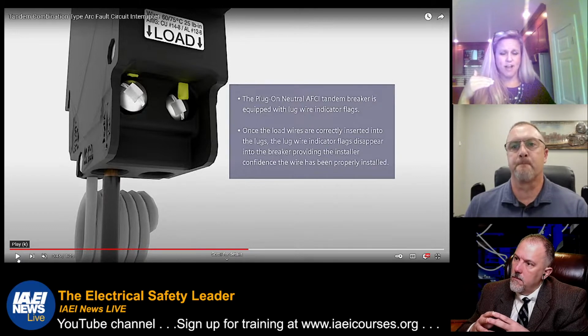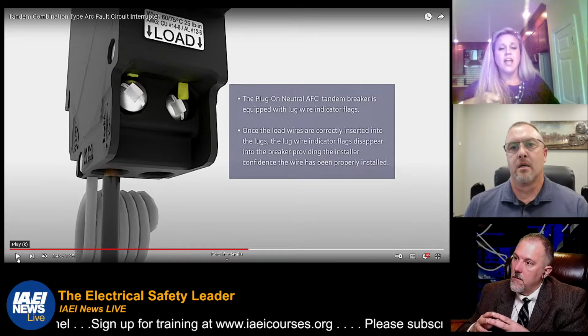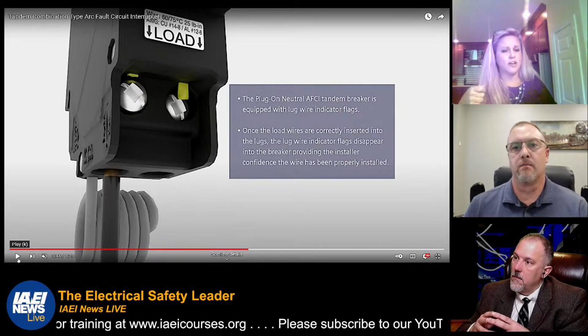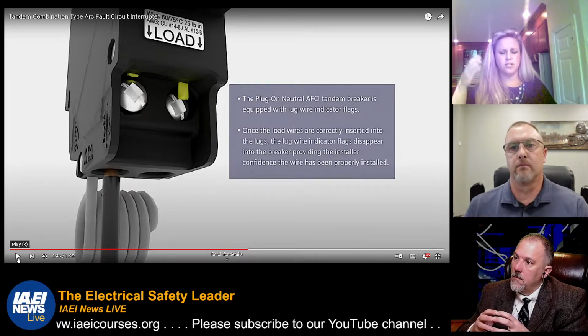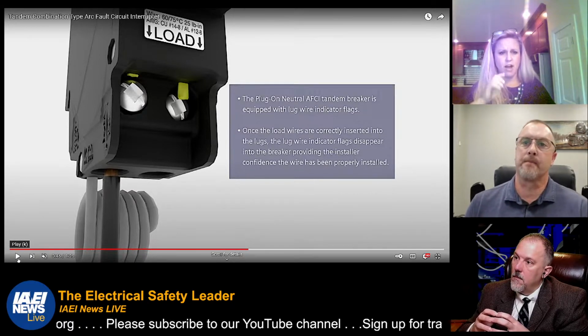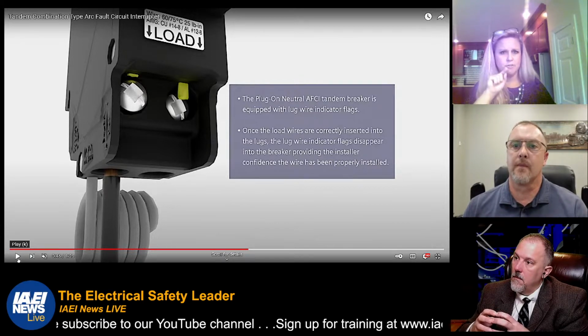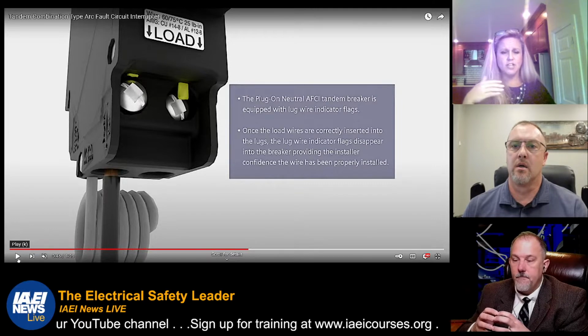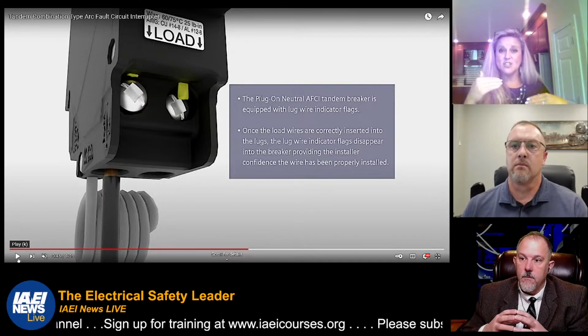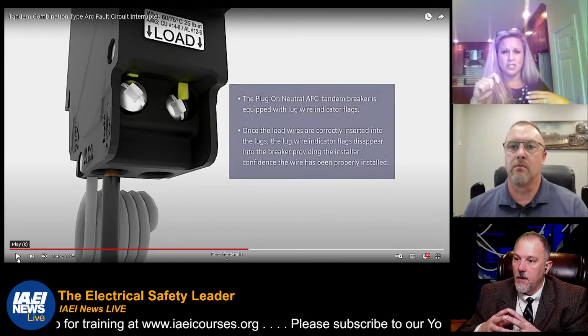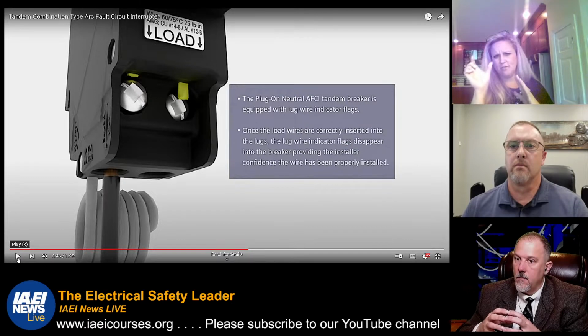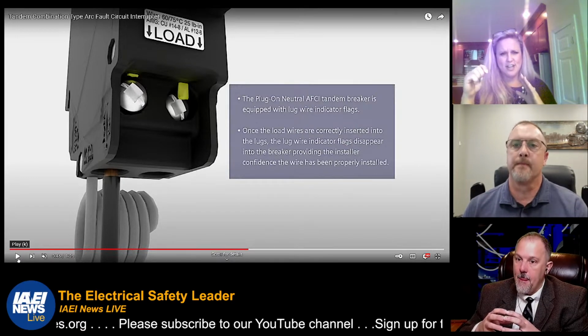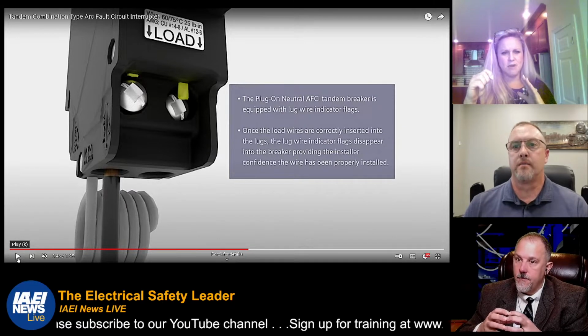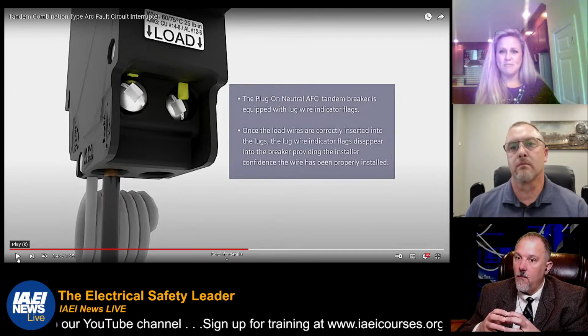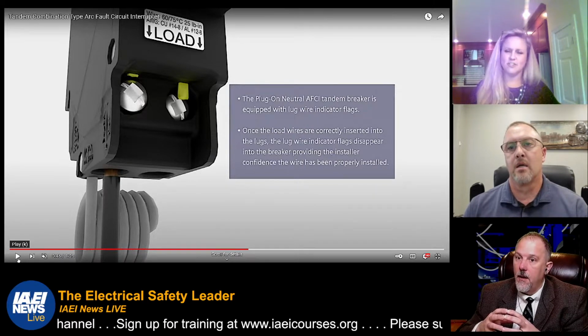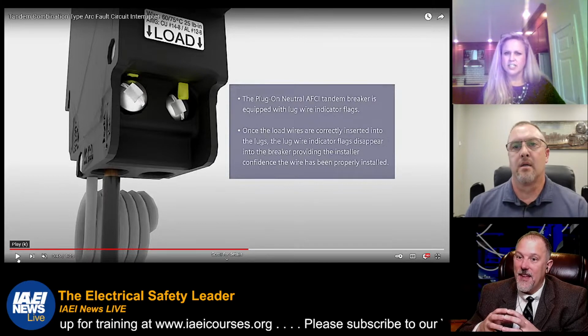Basically it's a yellow flag that comes up over the screw. Once you insert that load wire or that load neutral for the twin AFCI, you've got 2 loads because you've got 2 circuits. Once you insert that load wire, that flag, it's mechanical, just pushes back up into the breaker. And what it's doing is indicating that yes, you have wired that breaker correctly. You've put it in the right spot. A lot of times it's dark when these guys are working. You've got 4 inches of gutter space that you're trying to finagle that wire into, so you can push that wire in and that flag disappears, indicating, yep, you've got it in the right spot, and now you can tighten down your lug. Wow. What do you think of that, Donnie?